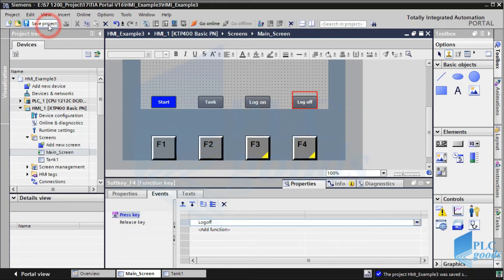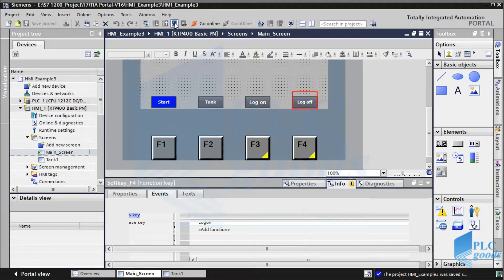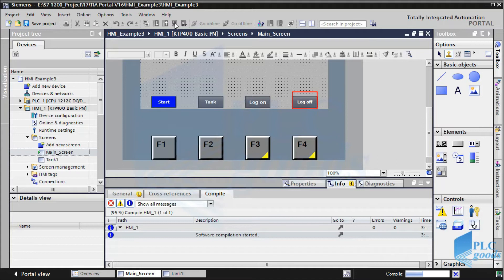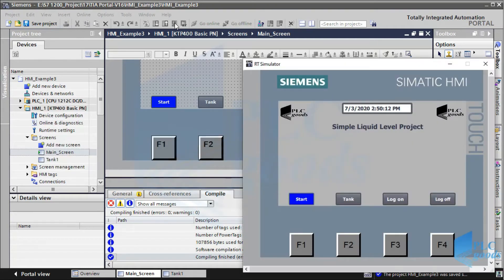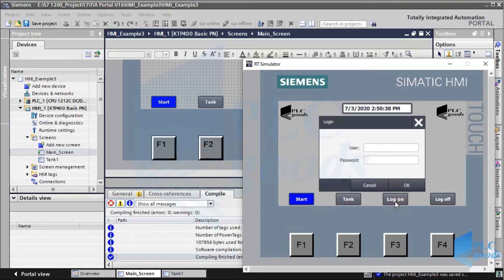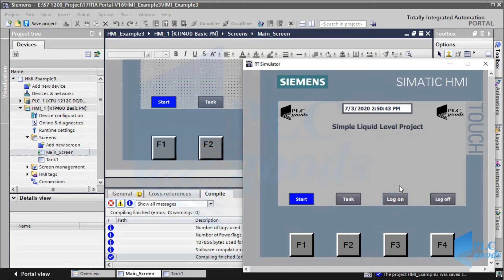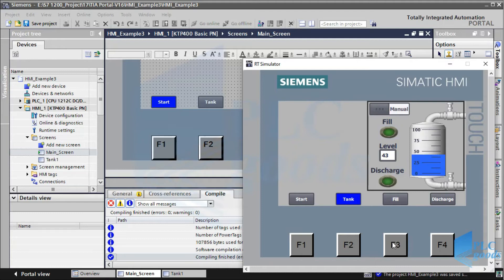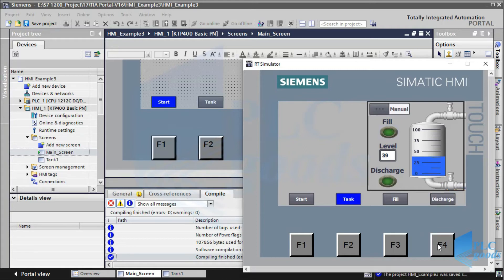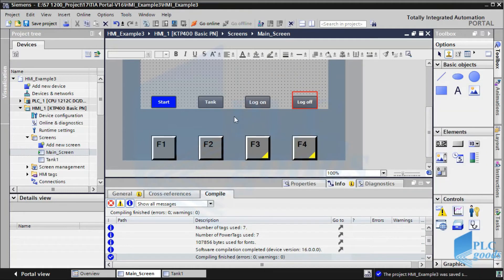Now let's test our HMI screens. As you see, the log on button and the F3 key open the login window on the start screen. In the tank screen, the F3 and F4 keys can be used to fill and discharge the tank. So F3 and F4 keys have different tasks in each HMI screen — this way of using function keys is called local assignment.